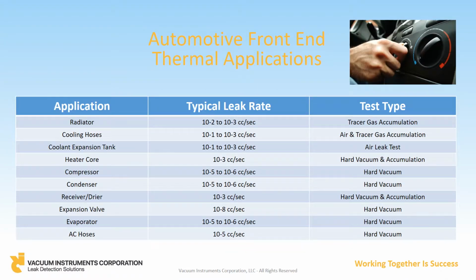Getting back to the thermal applications, here are examples of automotive front-end applications. The typical leak rate specification and the type of recommended testing methodology round out this slide. You will notice that within the group of products, there is over a 1 million times difference in sensitivity requirements, from 10 to the minus 1 cc per second to 10 to the minus 8 cc per second. Hence the advantage of having one technology to cover a myriad of related applications.